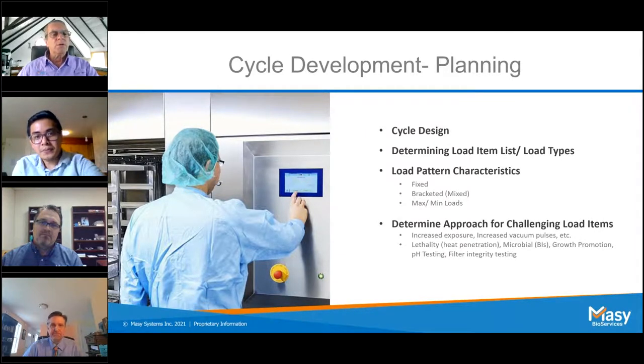Same quantity, location, and orientation, right? It's easy. However, the bracketing approach, or bracketing load, can be a variation of the fixed load, as a max with testing and utilizing a min to accommodate the production requirements. So it's kind of a variation on that. But then the bracketing load of any item, container size, volume of liquid within the container. You do want to pay attention also to how to prepare the item and establish your procedures.